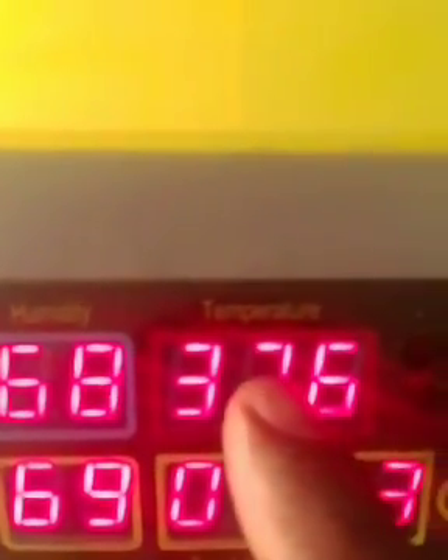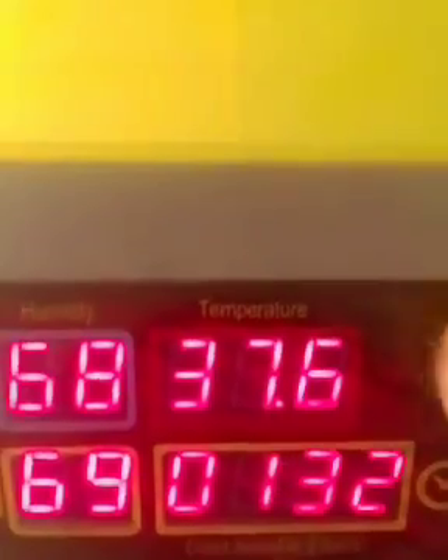This is the temperature control unit. Here you can see the temperature is set to 37.6 centigrade. This will swing between 37.4 and 37.6, giving you an average of 37.5. From time to time, it will come down to 37.4, then go up to 37.6, having an average of 37.5. This will make this particular chicken egg hatch in 21 days.